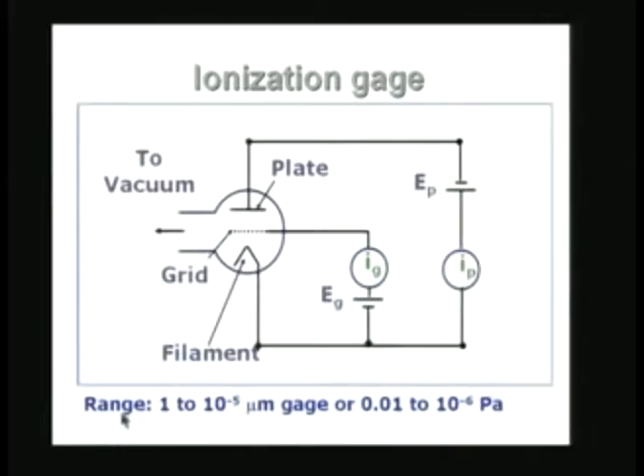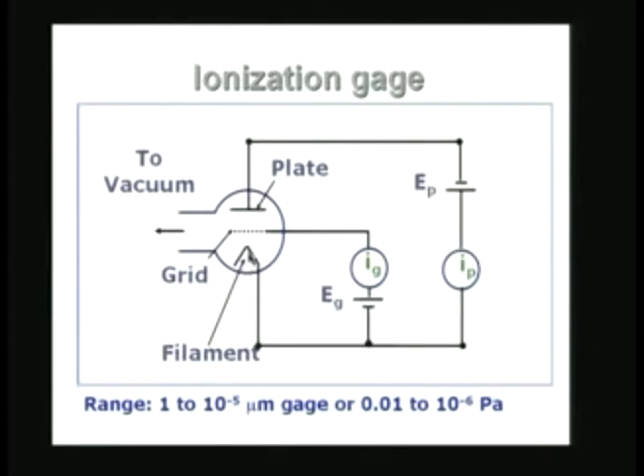For higher vacuum, I use an ionization gauge. The ionization gauge consists of an evacuated glass envelope containing three electrodes: a plate, a grid in the form of a perforated sheet or cylinder, and a hot filament which is the cathode. The filament is indirectly heated to a high temperature — it will glow like a filament in a bulb. This is a hot cathode type, which gives out electrons by thermionic emission.